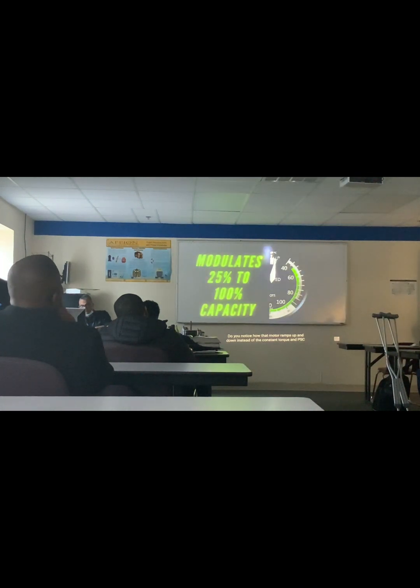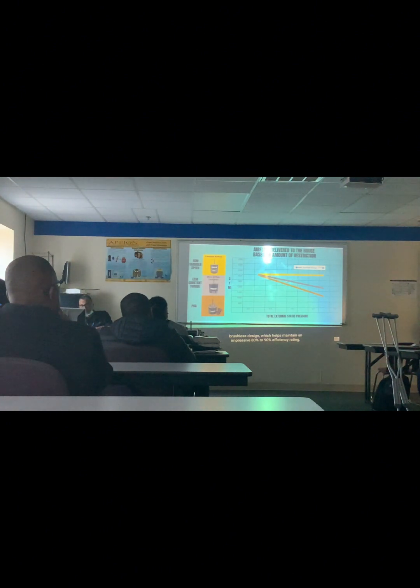You notice how that motor ramps up and down, instead of the constant torque motor and the PSC motors that have set speeds for specific demands from the thermostat? Variable speed motors can fluctuate between very low speeds and high speeds with their brushless design, which helps maintain an impressive 80 to 90% efficiency rate. When airflow in a variable speed system becomes restricted, airflow stays the same, constant airflow, because they've been programmed to know exactly how much torque and airflow the system needs to function properly. Constant torque motors can only apply a little more power to the blower wheel in an attempt to maintain the airflow needed by the system.